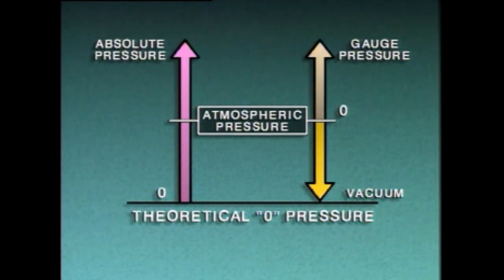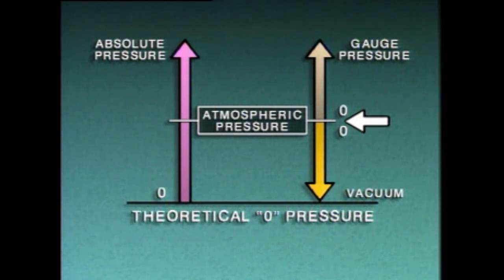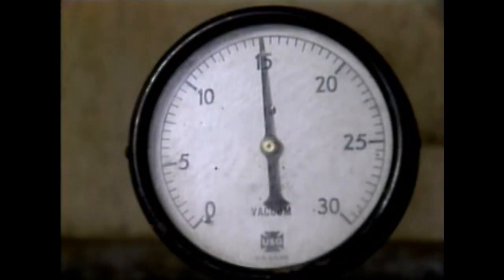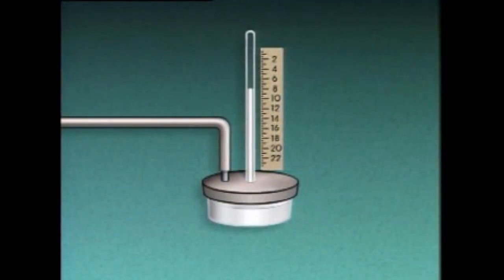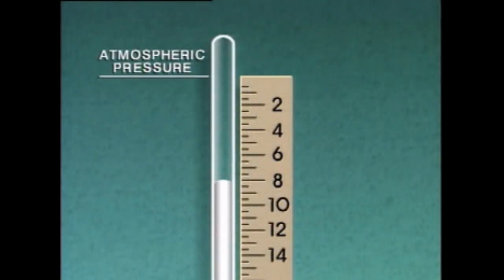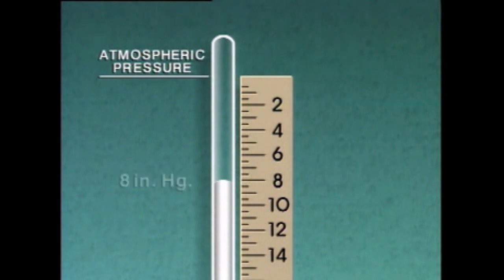The third pressure scale is the vacuum scale. Vacuum is pressure below atmospheric pressure. Like the gauge scale, the vacuum scale uses atmospheric pressure as its starting point, but it moves toward theoretical zero pressure. The closer it gets to theoretical zero pressure, the greater its value. On vacuum gauges, vacuum is often indicated in inches of mercury. This refers to the level of mercury in a vertical column measured downward from a level representing atmospheric pressure. If the level of mercury is 8 inches below the level representing atmospheric pressure, then the amount of vacuum is 8 inches of mercury, sometimes abbreviated inches Hg.